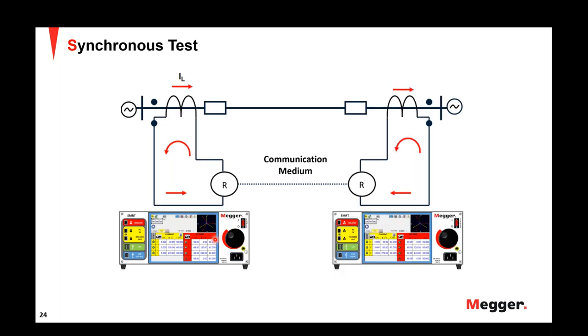The second type is, of course, the synchronous test. As the name suggests, synchronism is important. This is nothing but your end-to-end setup. Two test equipments injecting simultaneously at these relays, either the internal fault simulation or external fault, to validate the behavior of the scheme.